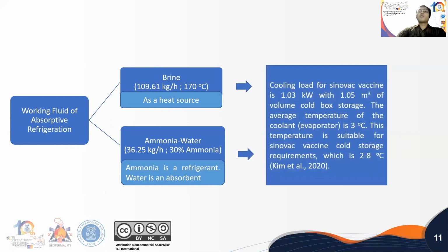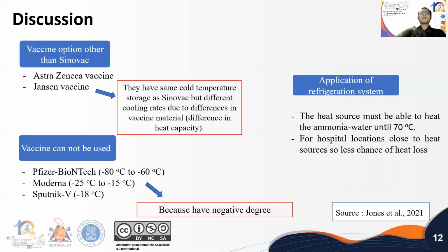So the cooling load for Sinovac vaccine, the vaccine that we use in the research, is 1.03 kilowatt with 1.05 meter cubic of volume cold box storage. The average temperature of the coolant or evaporator is 3 degrees Celsius. This temperature is suitable for Sinovac vaccine cold storage requirements, which is 2 until 8 degrees Celsius. And this is based on Kim research on 2020.